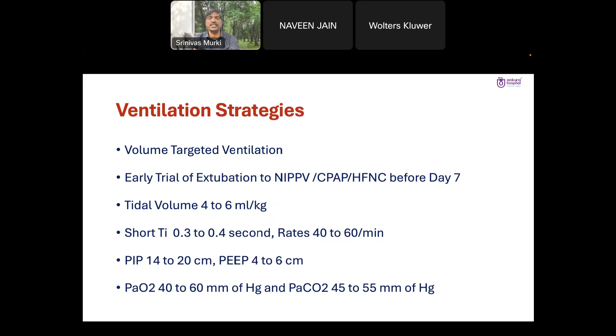And tidal volume, you can target 4 to 7. Avoid high tidal volume in the first few days because volume trauma is the worst trauma that can happen to premature babies. Use short TIs, rates of 40 to 60 per minute, and moderate pressures, with a pressure of 5 to 6, CPAP of 5 to 6. Your target PO2 should be between 40 to 60, and PCO2 should be between 45 to 50 mm of mercury.